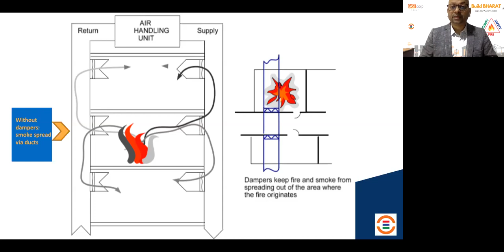Why don't we implement it? Because it needs coordination between HVAC and fire. And in fire, we just focused on fire sprinklers, hydrants, and fire alarms, not on this level of integration. We miss out. And that's how fire accidents happen, because we are not able to manage the smoke. And it's a very simple way to do it. If you look at the diagram, it is so simple. Just place the dampers, connect with the fire alarm systems, have the integration done, test the system well, see how you are going to manage your supply and return, finish. But it can save a lot of lives.